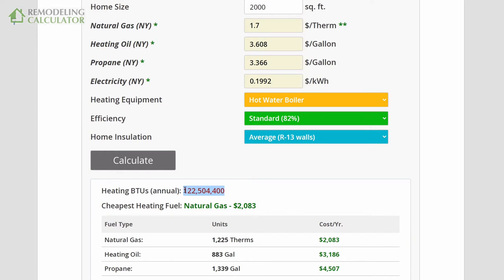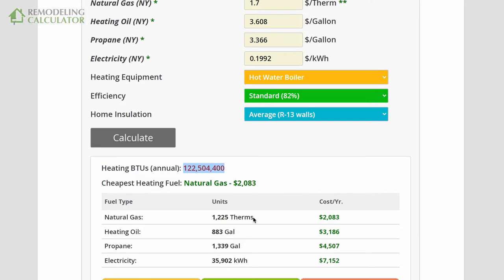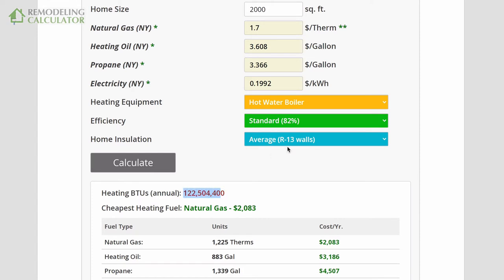This number shows your total heating BTU consumption per season — about six months, with three months of very high consumption and three months of relatively low consumption. We divide this total by the number of BTUs in each unit of heating fuel. For example, there are about 100,000 BTUs in one therm of natural gas — so dividing 122.5 million BTUs by 100,000 gives 1,225 therms. There are 140,000 BTUs in a gallon of oil, about 80-something thousand in a gallon of propane, and about 3,400 BTUs per kilowatt hour of electricity.